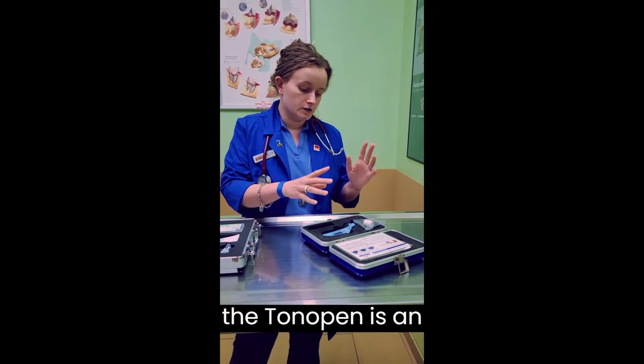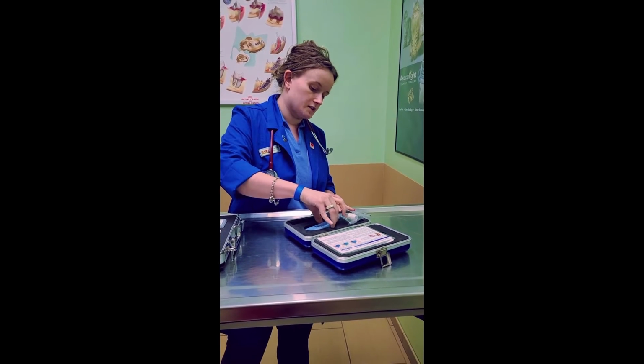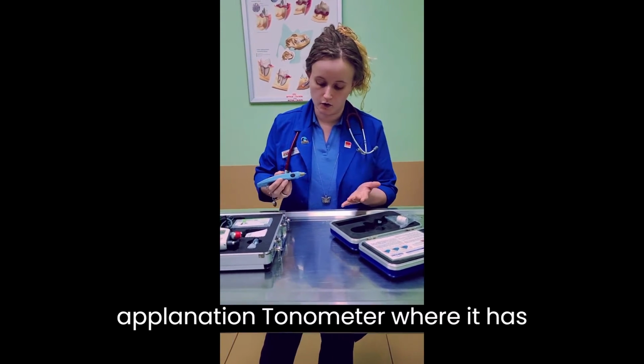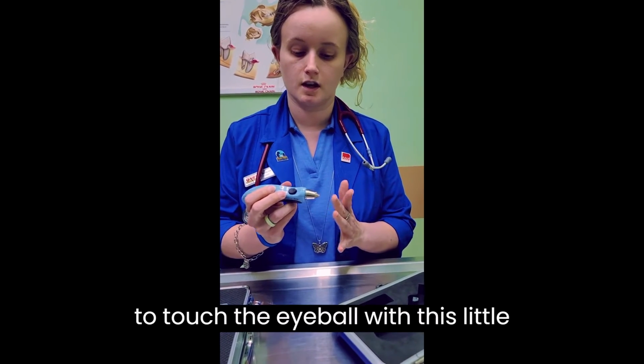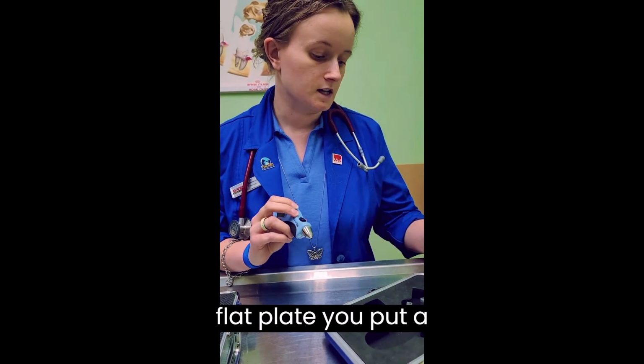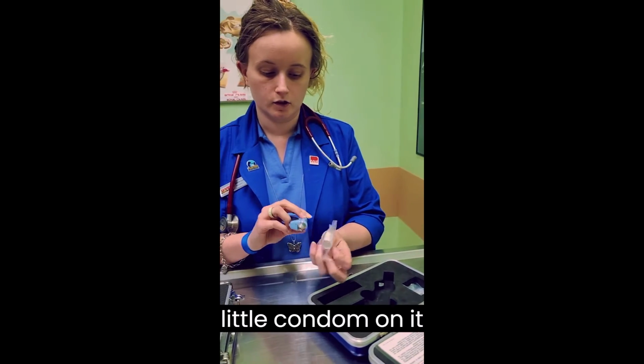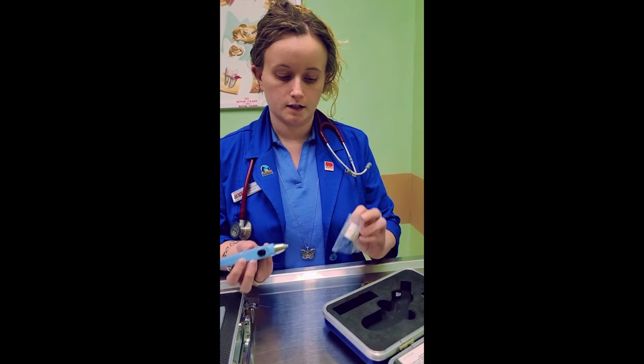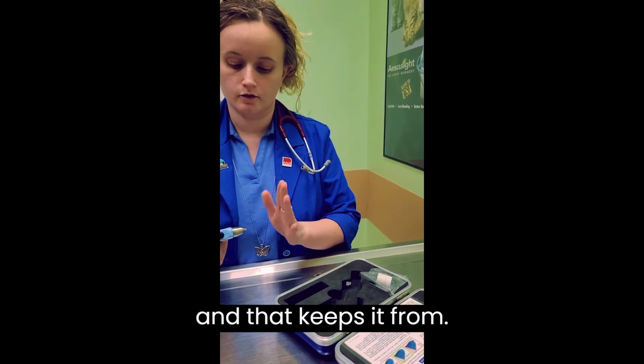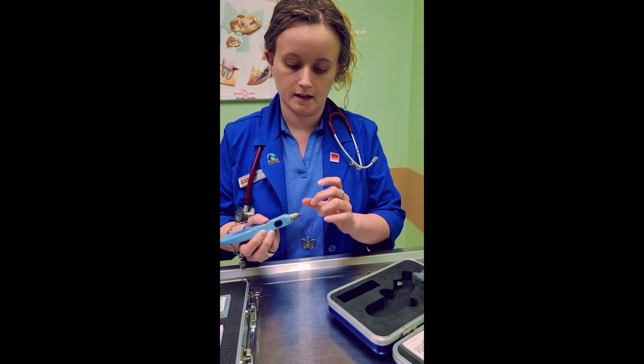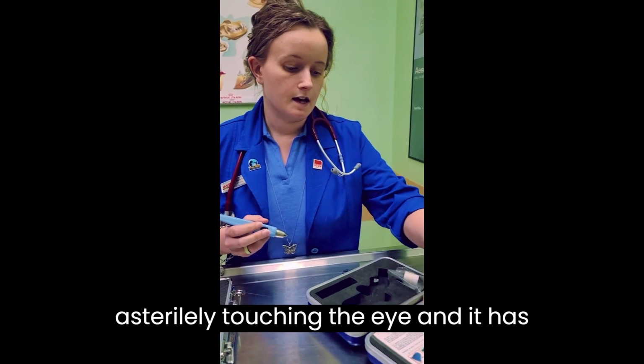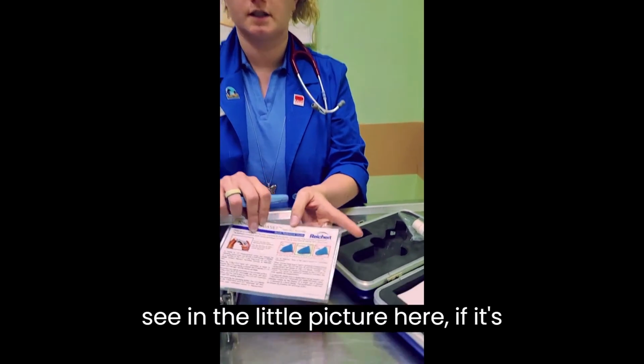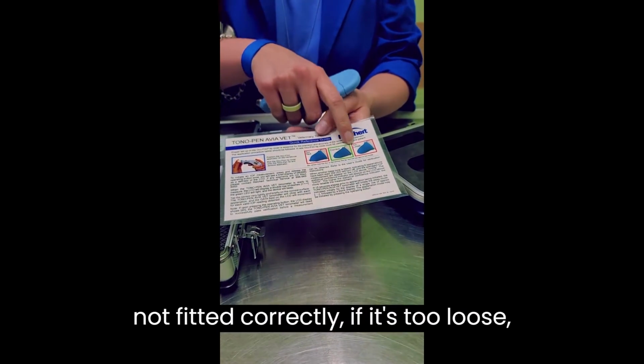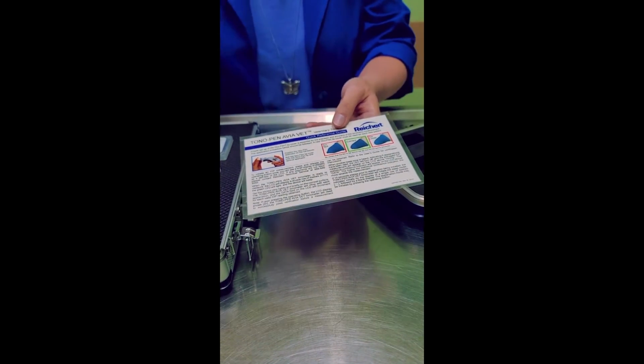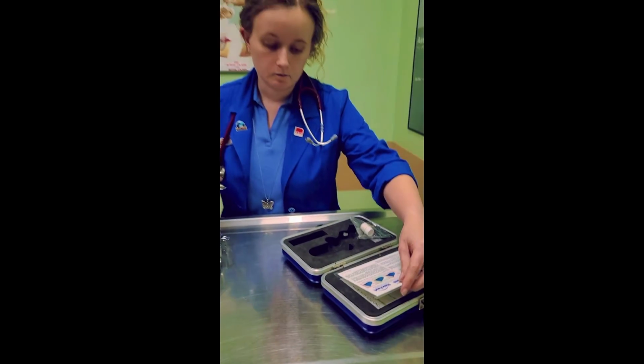So the TonoPen is an applanation tonometer, where it has to touch the eyeball with this little flat plate. You put a little cover on it, and that keeps it from directly touching the eye. And it has to be fitted correctly. So as you can see in the little picture here, if it's not fitted correctly, if it's too loose or too tight, it can affect your readings.